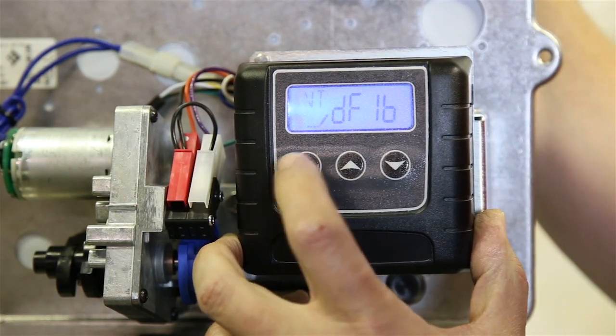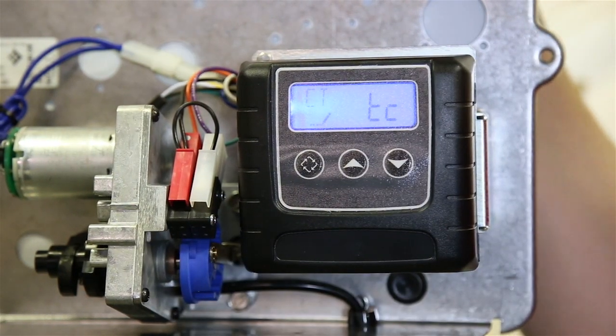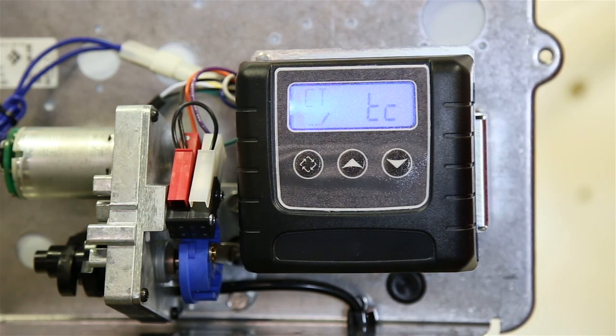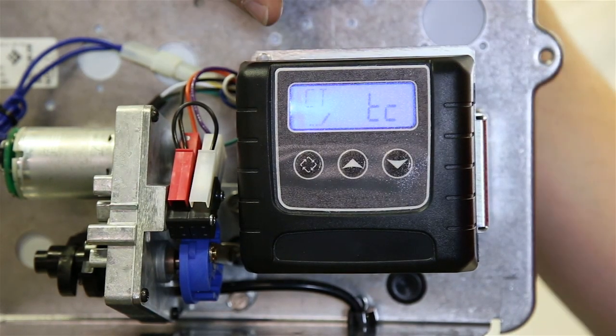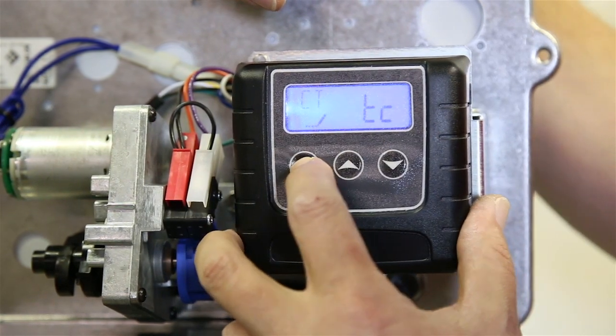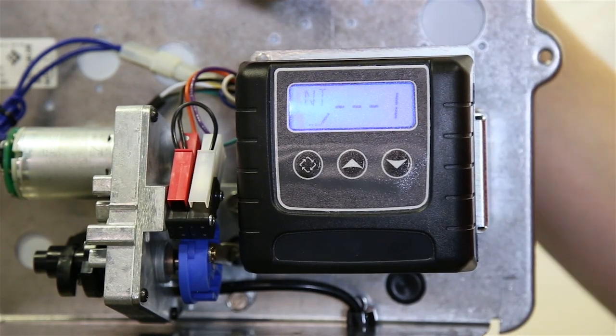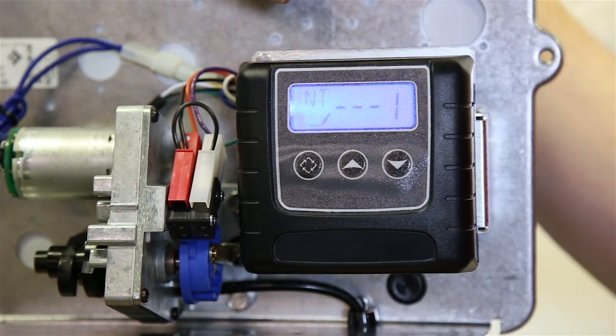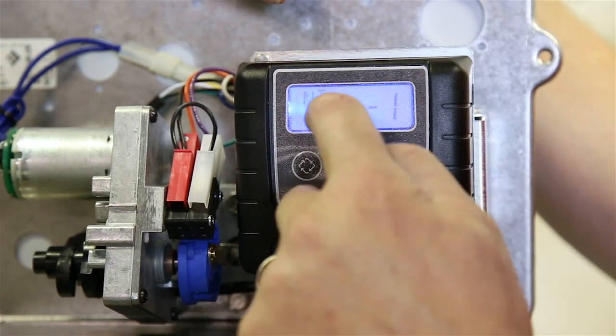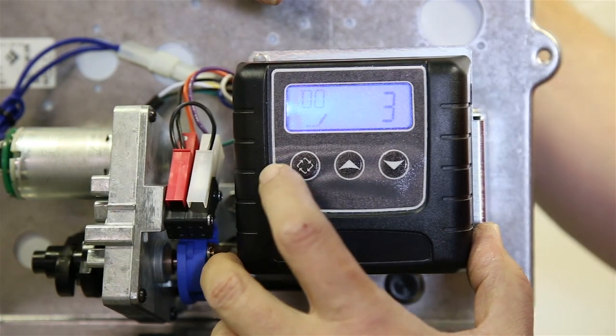The next one is control type. For this particular unit, we want to set it up as a time clock unit because we want this unit to regenerate based off of days between cycles. So we're going to leave that on TC for time clock and save it and go to the next parameter. The next parameter is number of tanks. And that represents the number of tanks below the actual control valve here. Since this is a single tank unit, that's why it says NT and then just one there.